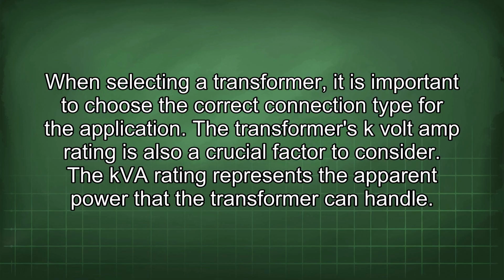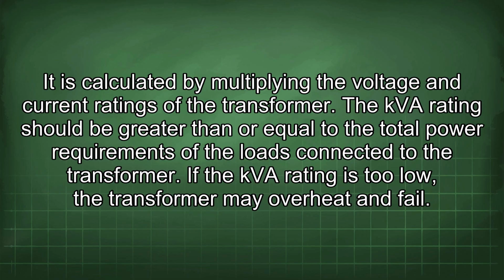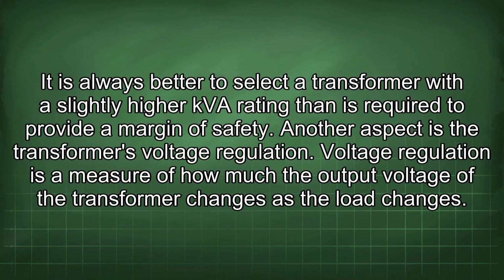The transformer's kVA rating is also a crucial factor to consider. The kVA rating represents the apparent power that the transformer can handle. It is calculated by multiplying the voltage and current ratings of the transformer. The kVA rating should be greater than or equal to the total power requirements of the loads connected to the transformer. If the kVA rating is too low, the transformer may overheat and fail. It is always better to select a transformer with a slightly higher kVA rating than is required to provide a margin of safety. Another aspect is the transformer's voltage regulation.